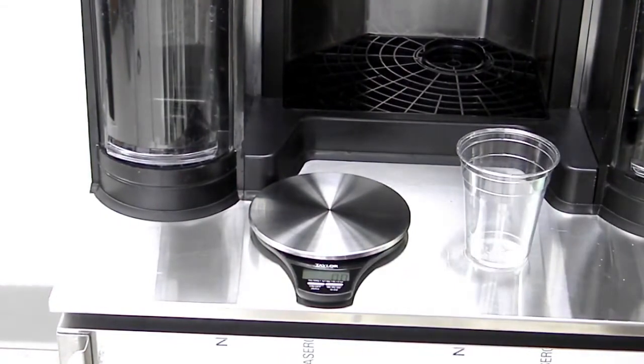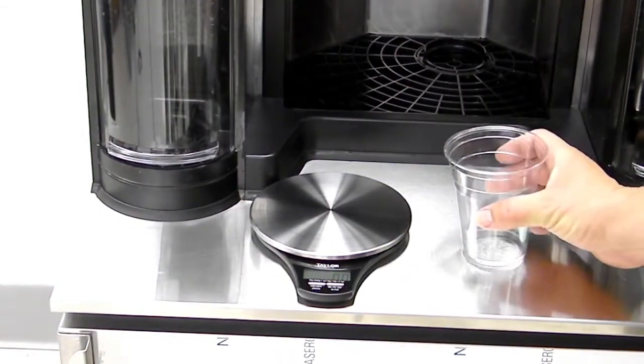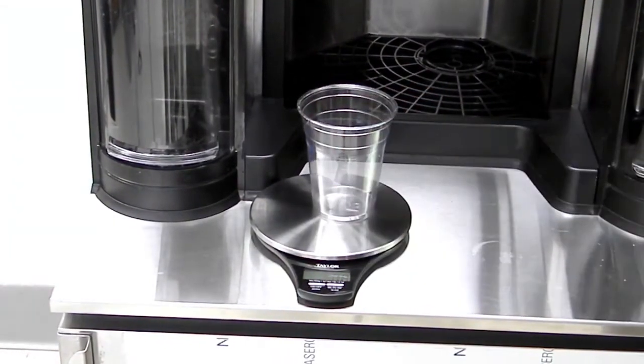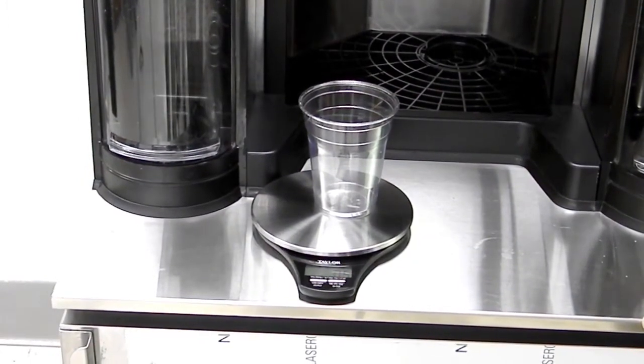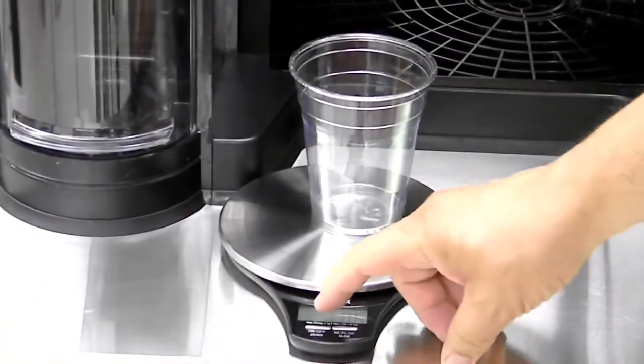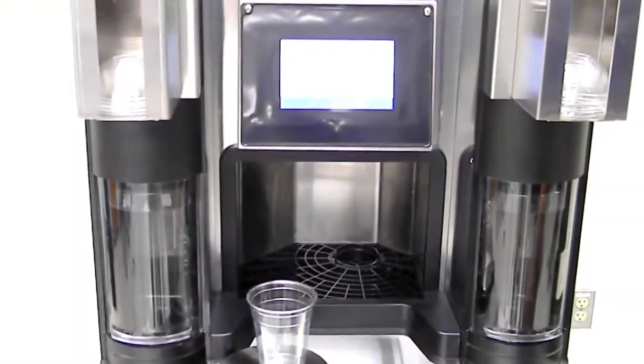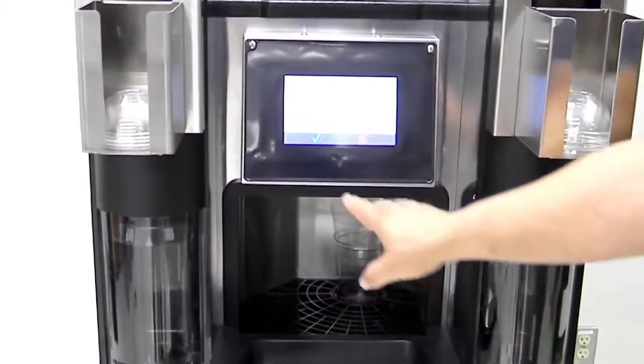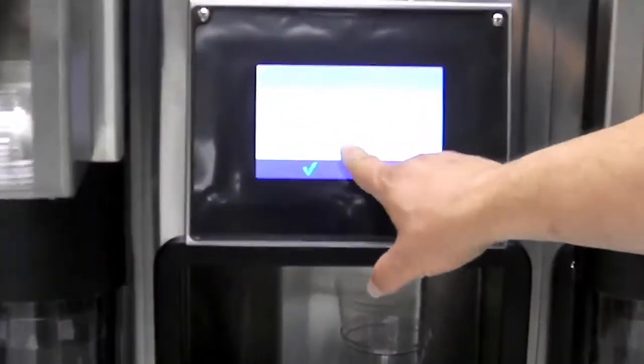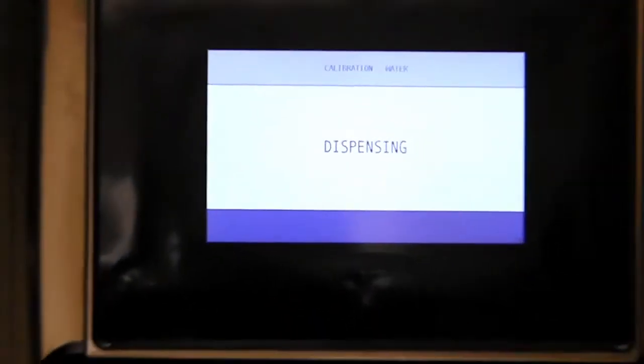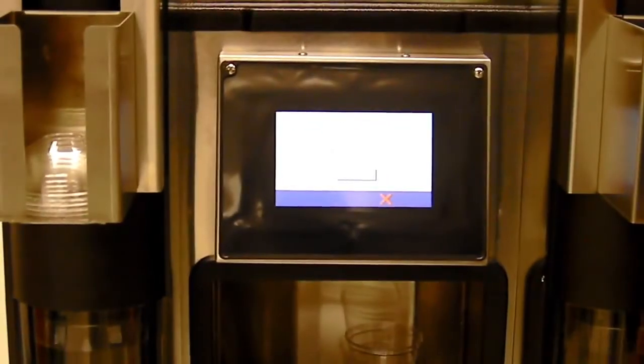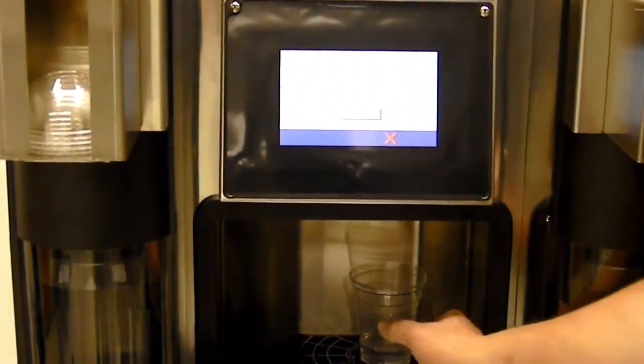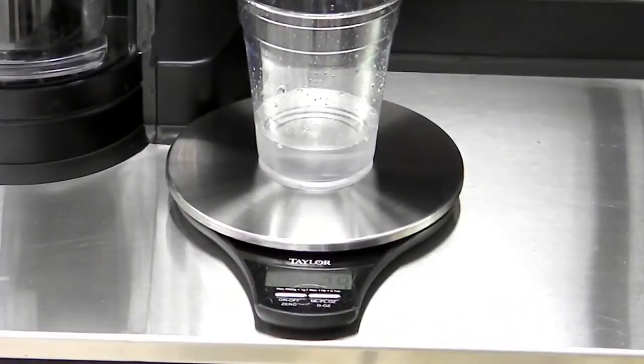Give the scale a minute to boot up. Move it to weighing fluid ounces. We're going to take our empty cup, put it on the scale, let it set, and then we'll zero it out once it records. Then we'll move the cup into position to dispense. We'll select the green check. You can see on the screen we followed all the instructions. Select the green check, the water will dispense. Now again, just reading off the instructions, it's going to tell us to move the cup back to the scale. I'm going to read the weight that was dispensed.